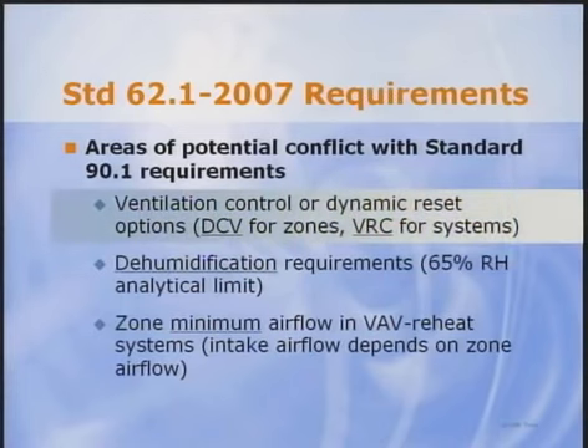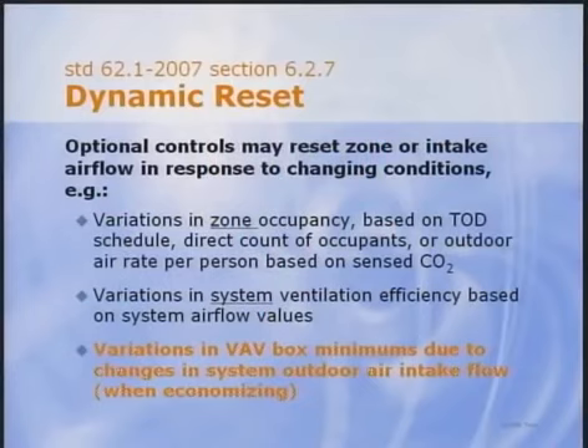We start with ventilation control, which Standard 62 calls dynamic reset. It takes energy to cool and dehumidify or heat outdoor air that's introduced into the building, so it's important to control it and avoid overventilation. In many buildings, the outdoor airflow needed at design conditions is quite high, but it drops off significantly at part load.